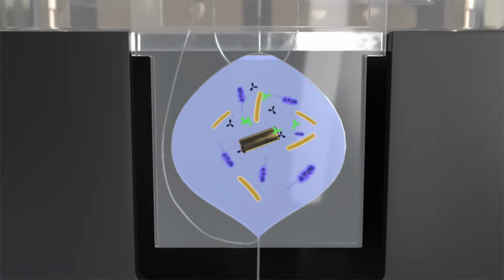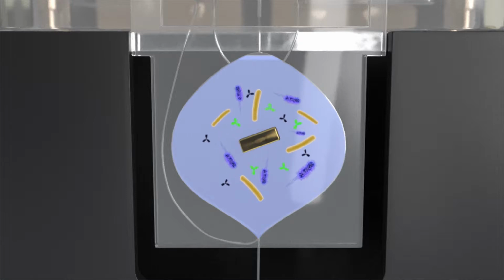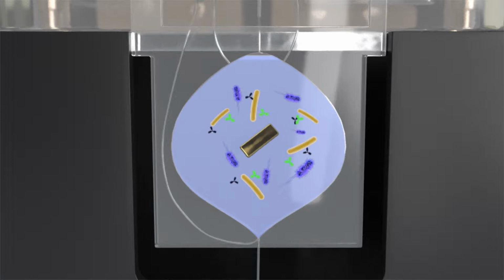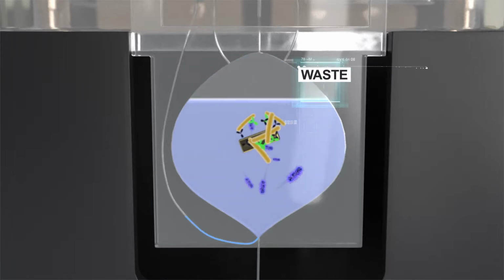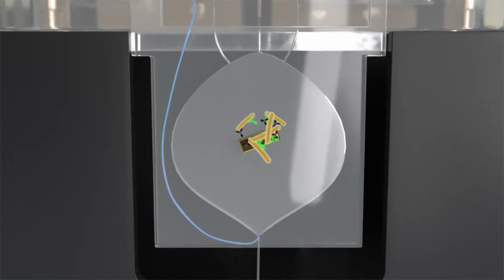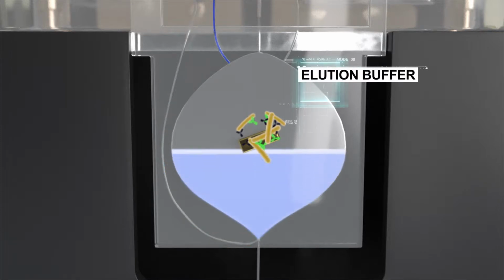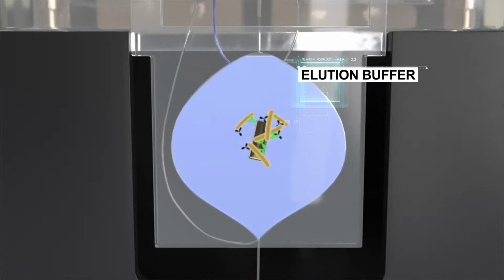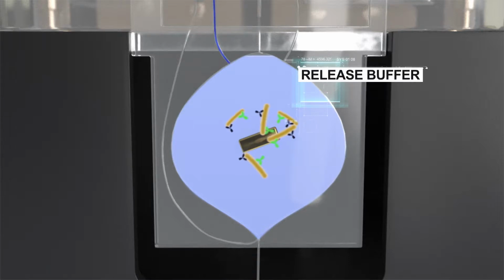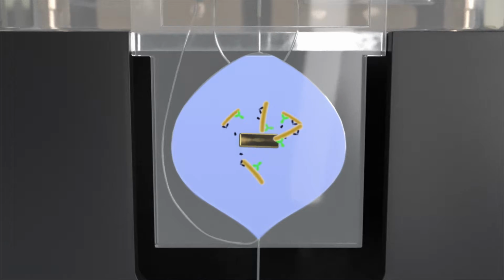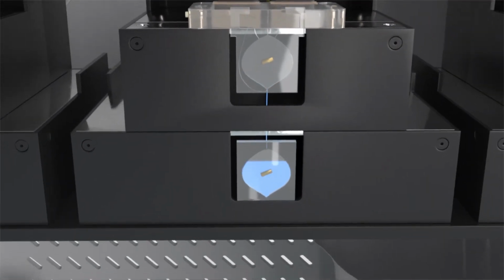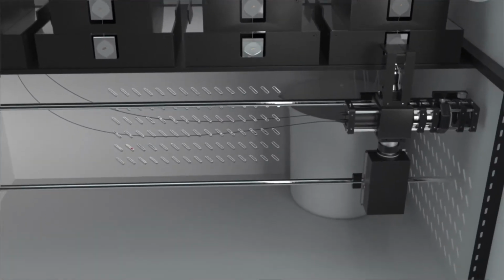After receiving the samples from the concentrator, the labeling of target bacteria with fluorescent and magnetic antibodies takes place automatically in the cartridges. Then, the stir bar inside the chamber mixes the sample by means of a magnetic system. Once the sample is mixed, supernatant is extracted through a specific channel, but the labeled microorganisms are kept inside the chamber due to the magnetic antibodies coupled to them. After the supernatant extraction, an elution buffer and a release buffer are added and the sample is mixed again. During this process, microorganisms are detached from the magnetic antibodies. Finally, the processed sample is transferred to the reading cartridge.